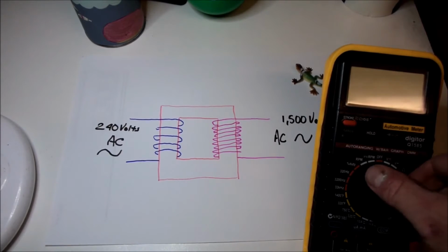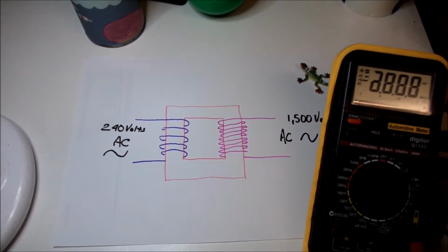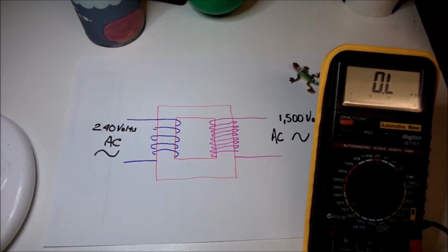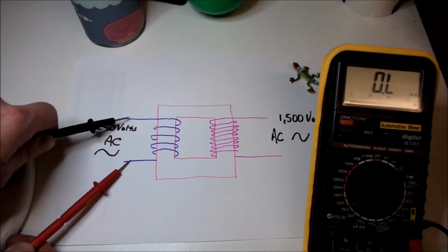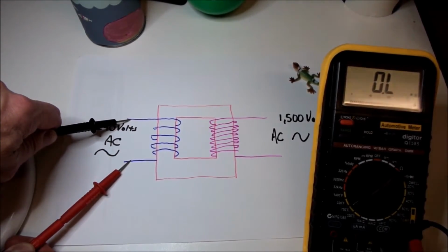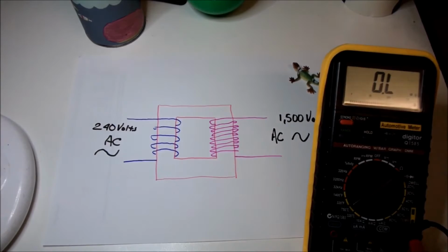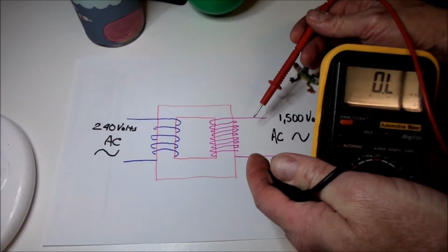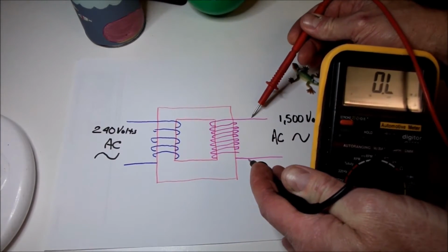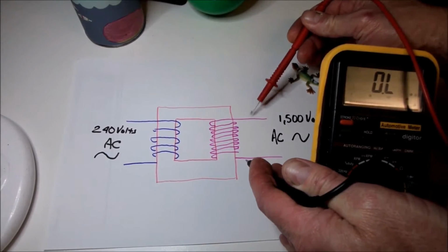For testing purposes, what we would do is turn it to ohms. We'd check across this wire and this wire to see if we had continuity, and then on the secondary, because it's a single wire, we check there, and that will tell us if we have continuity or not.